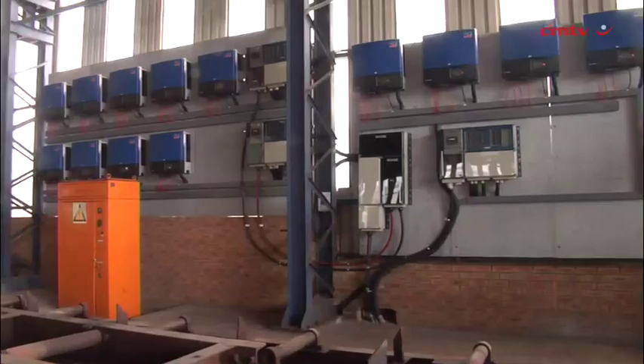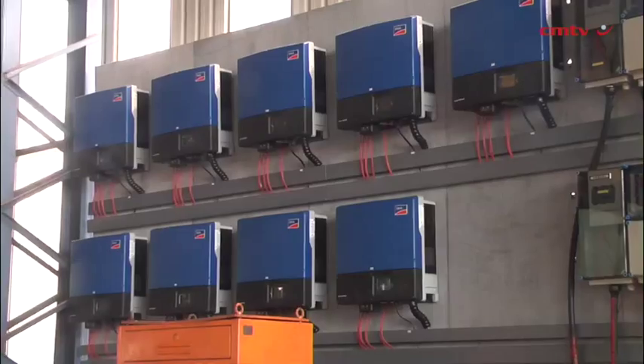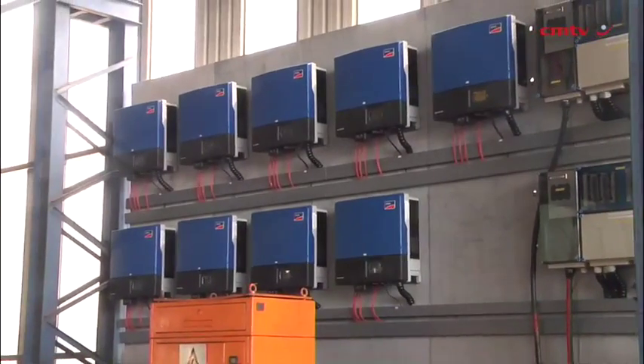It only works supplementing with Eskom. It's a 352 or 353 kilowatt system. The number of modules is 1,400 PV modules, each sized at 255 watts. We use mainly SMA inverters — most of the bulk are 17 kilowatt inverters, with smaller inverters as well, sized accordingly.